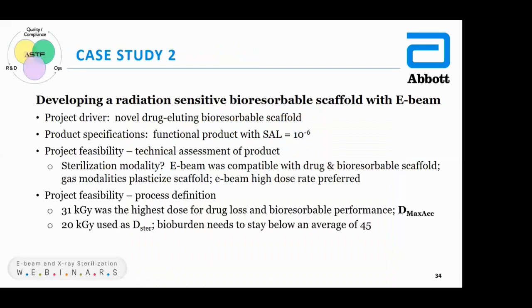So now in terms of project feasibility, specifically the process definition we had up on the screen earlier—the establishment of the max acceptable dose and the sterilization dose—as I mentioned, 31 kilogray was the highest dose for drug loss and bioresorbable performance, so Dmax acceptable was defined as 31 kilogray.